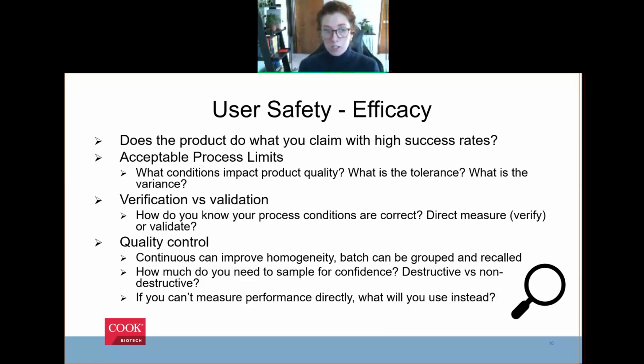Another potential example of validation is packaging. So when we package our devices, we put them into pouches that have to maintain that sterile barrier. And the ability of that barrier to stay closed depends on things like the pressure of the seal, the temperature of the seal, other factors like that. But we can't test that without destroying the package. So we validate the sealing conditions to be confident that if we operate this equipment at this temperature, at this pressure, it will create these conditions to create a sterile barrier.